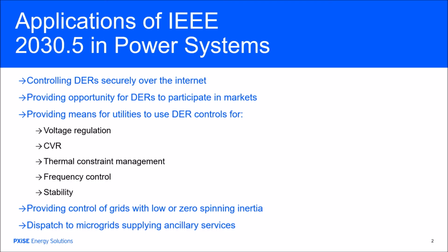So there's quite a number of potential applications of the technology. Many of these are actually outlined in the specifications itself, but there's some other applications that can be used using the functions of the standard. In particular, there's a function called the meter mirror, which allows a server to collect data from clients of any type at any rate. And this information can be used to apply direct controls to the grid through the DERs.